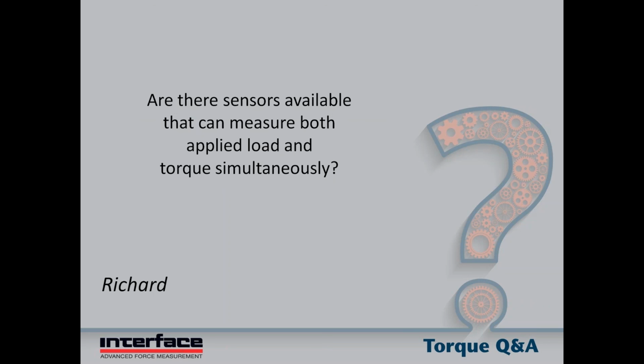Next question. Are there sensors available that can measure both applied load and torque simultaneously? Yes, there are. Typically, Interface calls those types of sensors axial torsion. In most cases, they are static or reaction type torque sensors in that they don't rotate, or they only rotate through limited range. The reason for that is typically if you have bearings, then you also have to allow the force to be transmitted through the bearing into the measuring section, which can be done, but it complicates things somewhat.